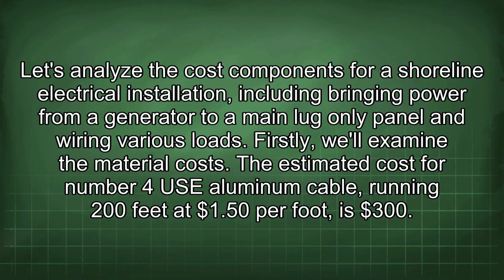Let's analyze the cost components for a shoreline electrical installation, including bringing power from a generator to a main lug-only panel and wiring various loads. Firstly, we'll examine the material costs. The estimated cost for number 4 USE aluminum cable running 200 feet at $1.50 per foot is $300.